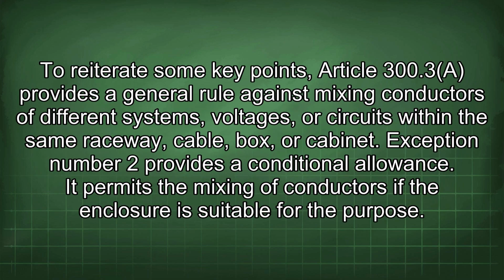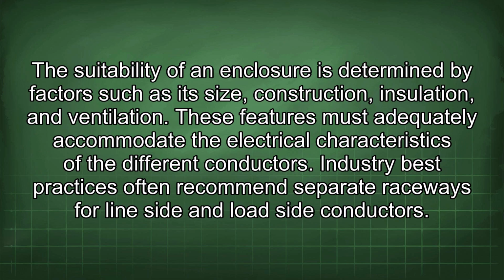To reiterate some key points, Article 300.3 provides a general rule against mixing conductors of different systems, voltages, or circuits within the same raceway, cable, box, or cabinet. Exception number 2 provides a conditional allowance. It permits the mixing of conductors if the enclosure is suitable for the purpose. The suitability of an enclosure is determined by factors such as its size, construction, insulation, and ventilation. These features must adequately accommodate the electrical characteristics of the different conductors.